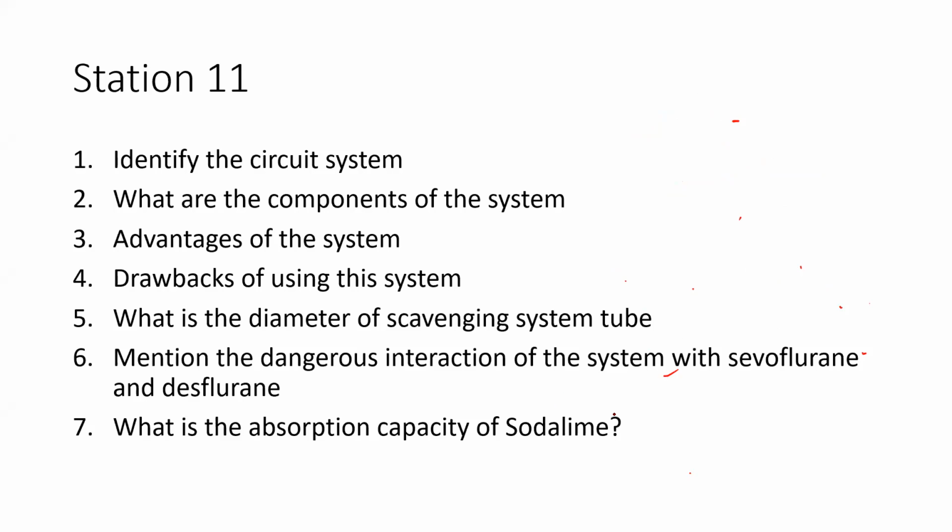Good. What is the absorption capacity of the soda lime? 1 kilogram of soda lime can absorb 120 liters of carbon dioxide. Okay, this is the normal absorption capacity of the soda lime. So what are the normal contents in the soda lime?